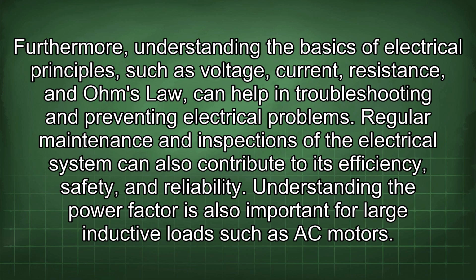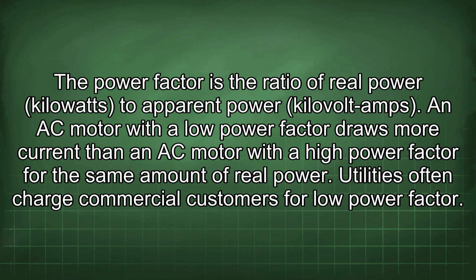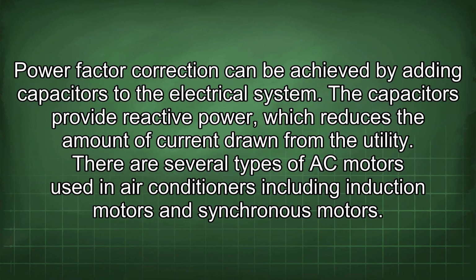Understanding the power factor is also important for large inductive loads such as AC motors. The power factor is the ratio of real power, kilowatts, to apparent power, kilovolt-amps. An AC motor with a low power factor draws more current than an AC motor with a high power factor for the same amount of real power. Utilities often charge commercial customers for low power factor. Power factor correction can be achieved by adding capacitors to the electrical system. The capacitors provide reactive power, which reduces the amount of current drawn from the utility.